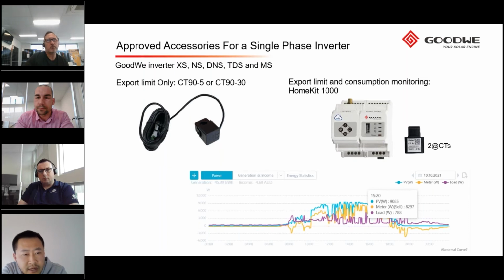So if the customer wants to do export limit, they just need to purchase this CT90 clamp. Currently we offer two versions of CT90. The most popular one is CT90-5, which means the CT is 5 meters in length. And if in your installation job the meter box is longer than 10 meters away from the inverter, then usually you can select CT90-30, which is the 30 meter length CT clamp.